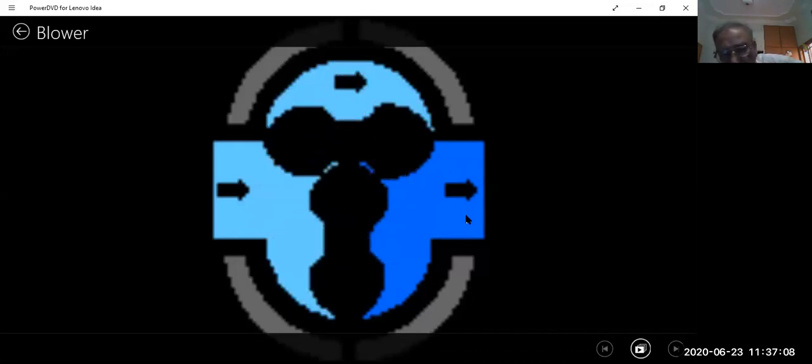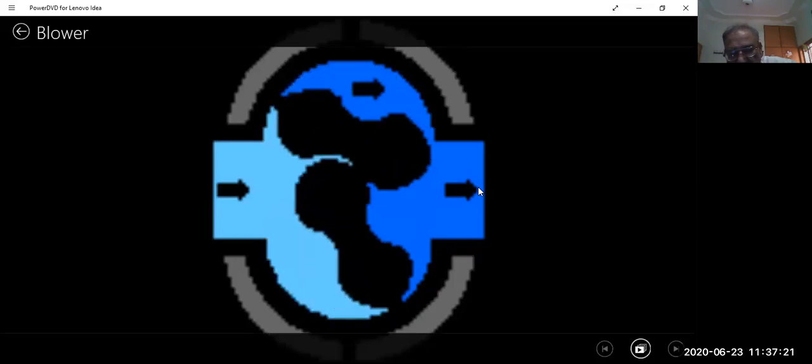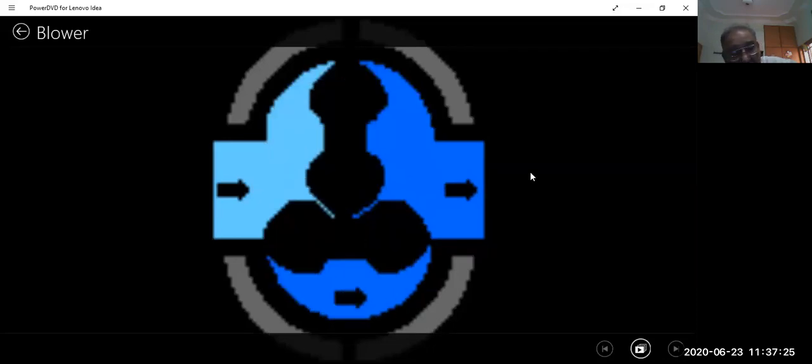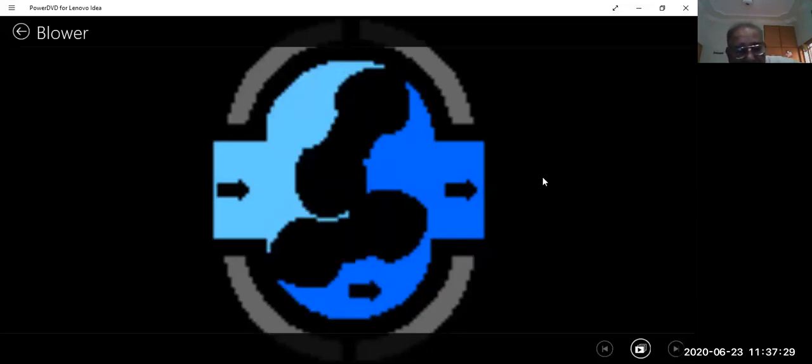So actually they just push, they do not compress at all. Inside the cylinder, the compression process does not take place at all. So they just throw it from left side to right side. And when the right side is open from this lobe, the right side is the receiver. Receiver is the high pressure side.